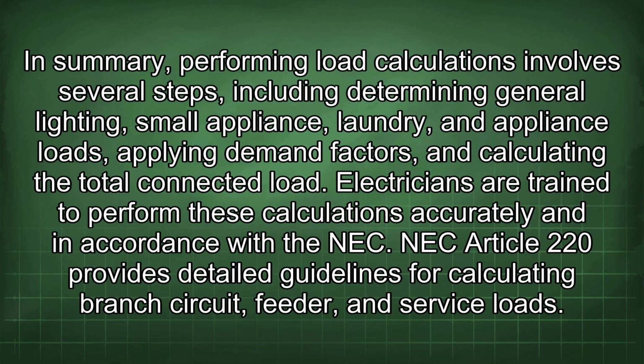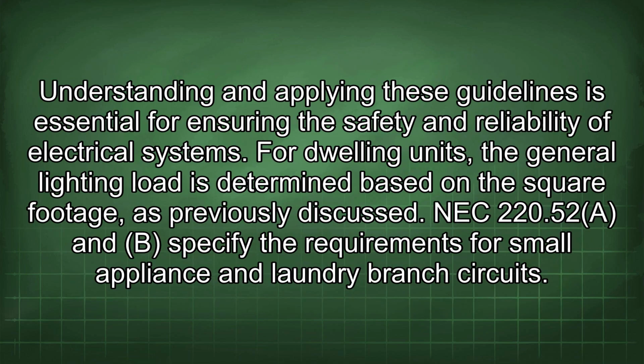In summary, performing load calculations involves several steps, including determining general lighting, small appliance, laundry, and appliance loads, applying demand factors, and calculating the total connected load. Electricians are trained to perform these calculations accurately and in accordance with the NEC. NEC Article 220 provides detailed guidelines for calculating branch circuit, feeder, and service loads. Understanding and applying these guidelines is essential for ensuring the safety and reliability of electrical systems.